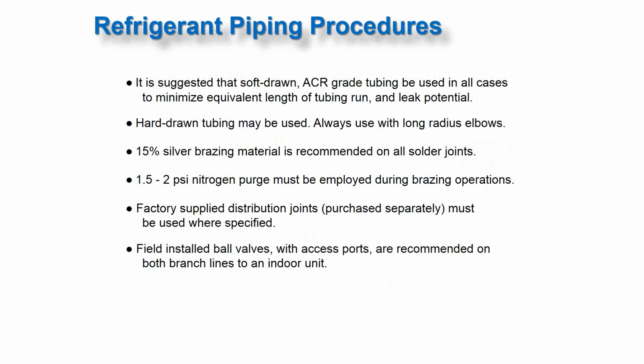Okay, just want to talk about refrigerant piping procedures. We always want to use insulated, soft drawn, flexible copper for your refrigerant runs. It has to be ACR grade, obviously. The refrigerated lines, we want both of our liquid and suction lines insulated. You see a lot of VRF manufacturers, they want to see white, the easy pull line sets for ductless. That's the best option to use.